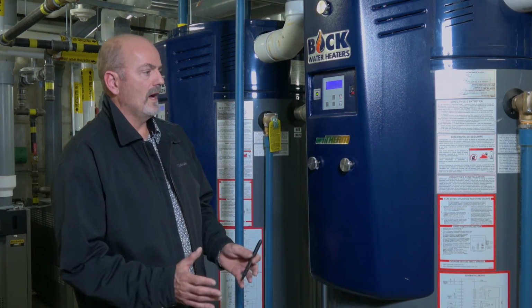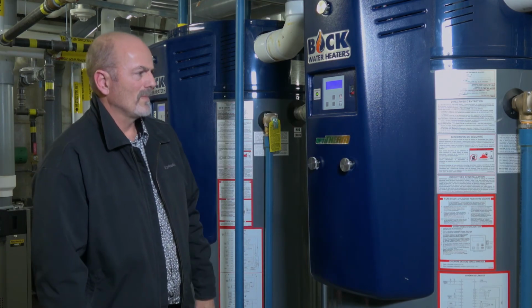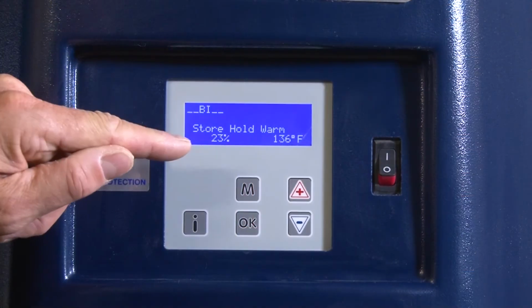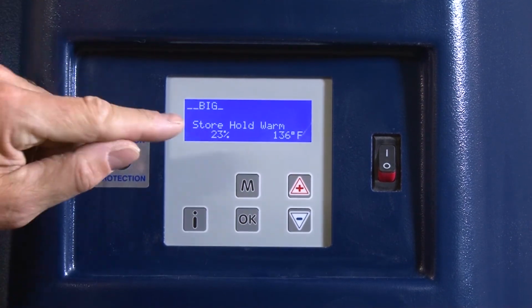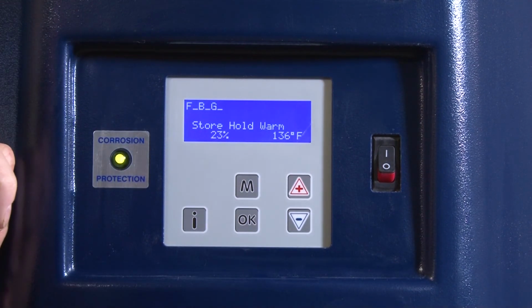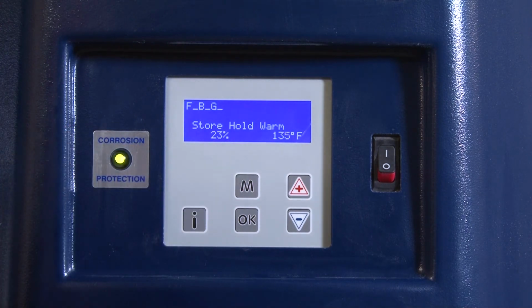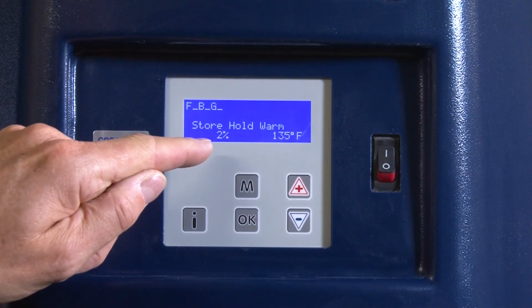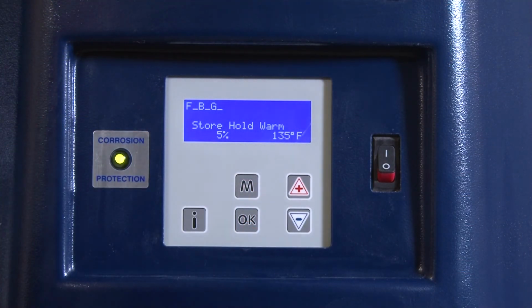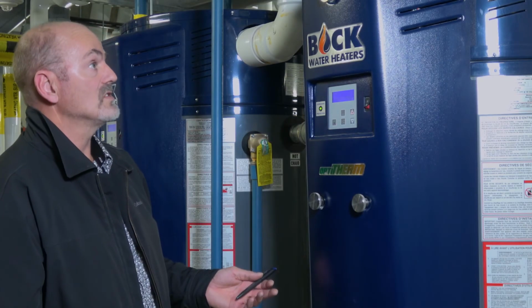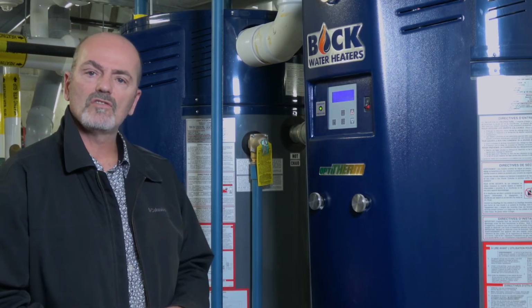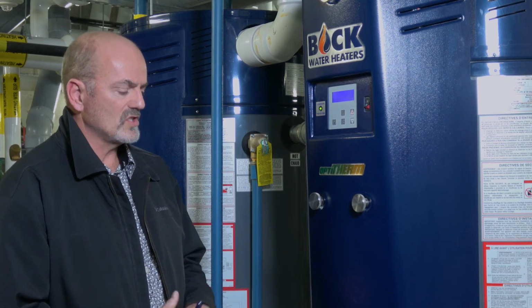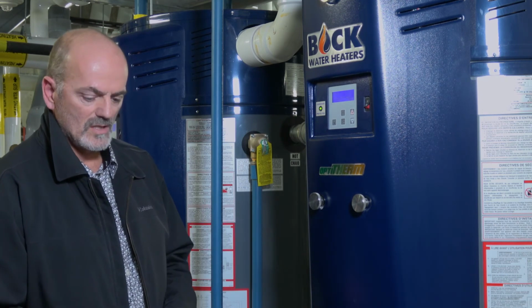Okay. Other than that, the main display tells you when it's running. Right now, it's the store hold operating at 23% of its capacity, and it's working, and it's got a current temperature in the tank of 135. It will probably fire up to bring its store hold down. It will fire up shortly as that temperature drops. And if the temperature rises closer to set point, it modulates down and then shuts off. And that's essentially it.